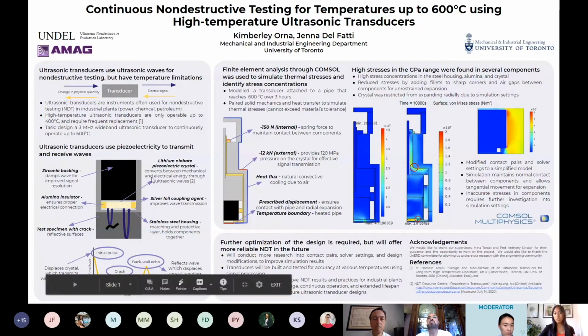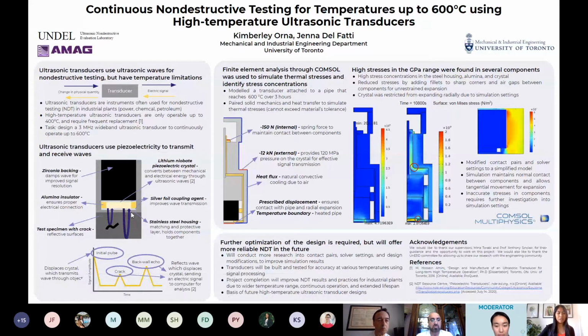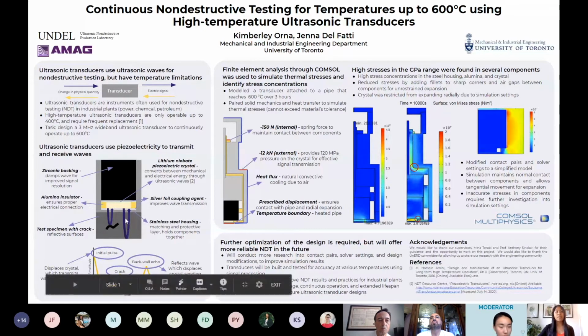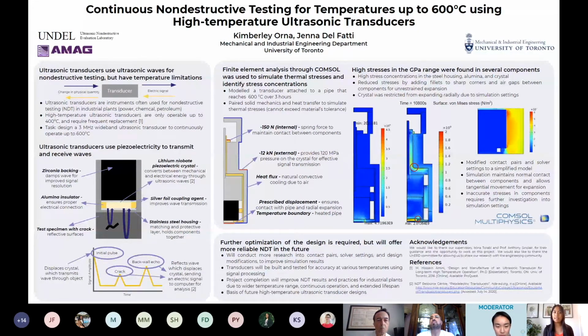Some basics into how ultrasonic transducers work. I hope you can see my cursor, but there's an element here called a piezoelectric crystal that basically converts the electric signal into an ultrasonic wave. So an initial pulse is sent out to this crystal, and it creates and transmits an ultrasonic wave that goes into this test specimen, bounces off a crack or the back surface. The reflected wave is then absorbed by the crystal, which converts that into an electric signal that is sent out to a computer that is processed and analyzed.